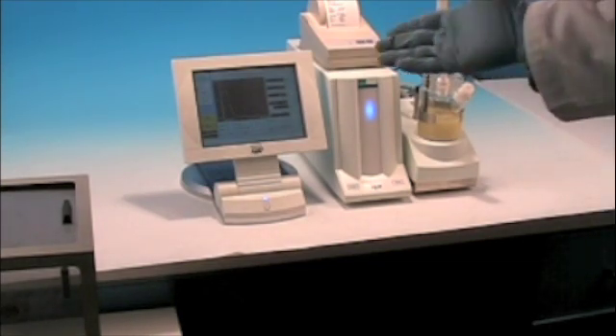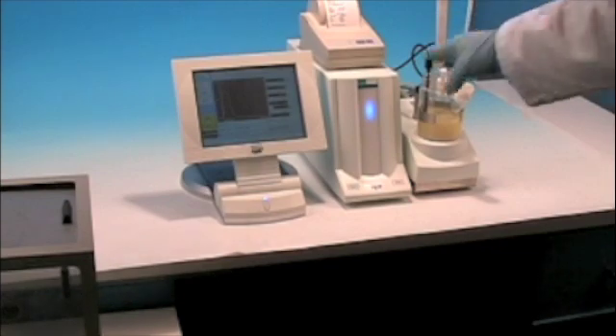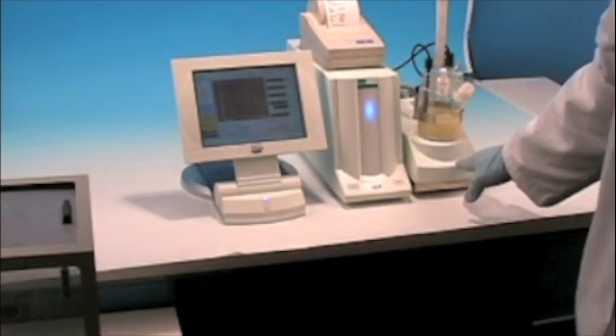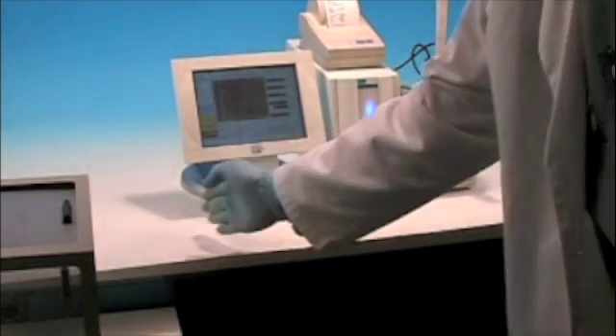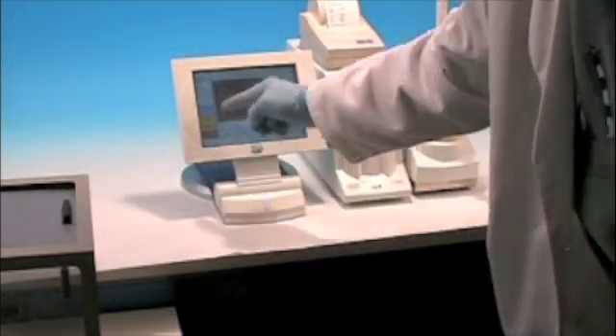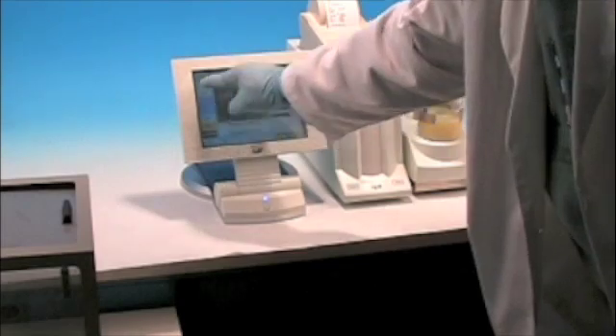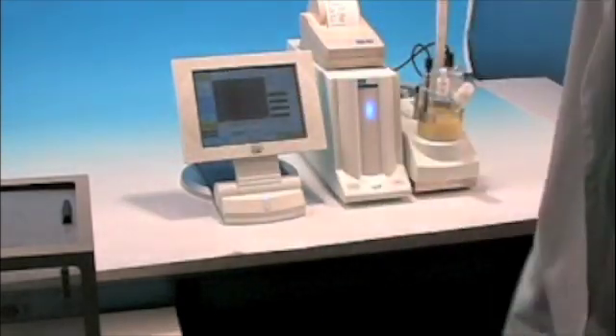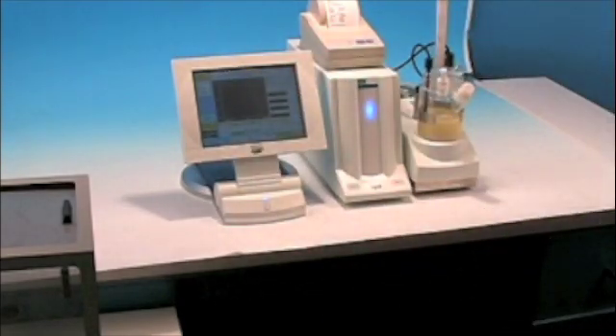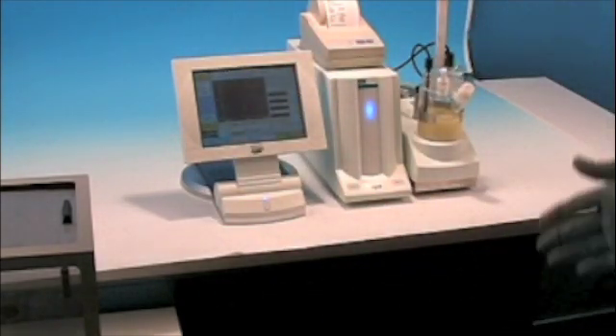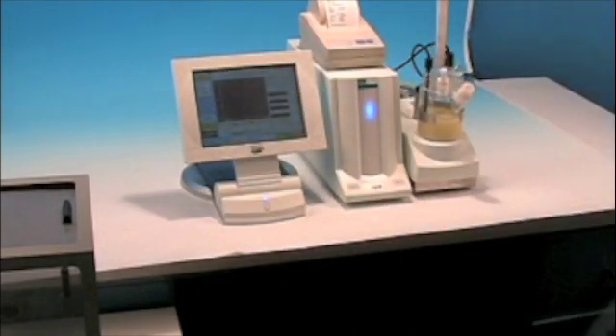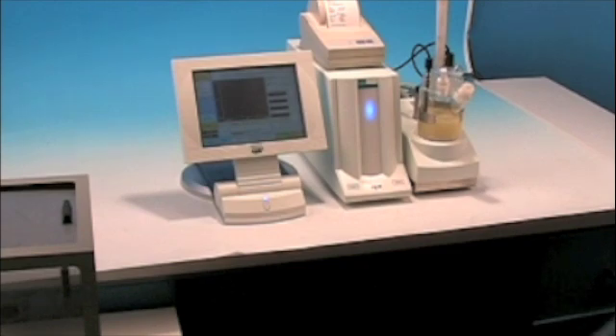This unit can have two titrators hooked up and run simultaneously by simply toggling between the two titrators. So you can run two Karl Fischers. For that matter, you can run a potentiometric if you wanted to.